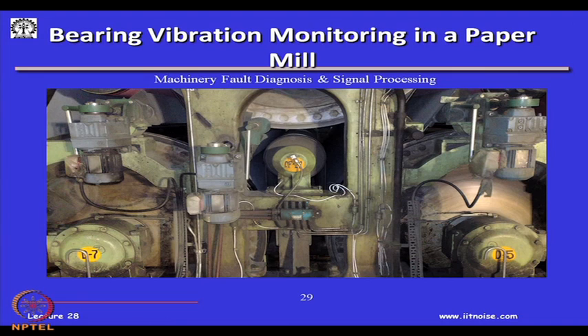And then there are diagnostic algorithms wherein people can know which vibration signal is coming from which bearing, what its kurtosis value is, and what its spectrum value is. These are very, very critical operations. Imagine if one roll breaks and falls, it is going to damage a few other rolls and a few other bearings, and to put everything together, you can imagine the problem one has to face. So, depending on the criticality of the equipment or the process of the plant, monitoring of rolling element bearings is essential. Particularly in paper mills, this monitoring is sometimes done continuously online.